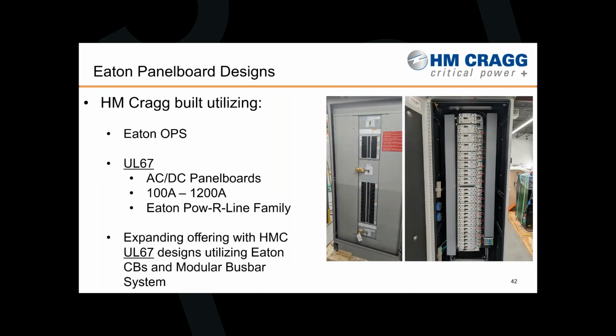When it comes to panel boards, we're utilizing a lot of the Eaton OPS program to develop distribution around them. As mentioned previously, we use panel boards in switchboard designs, which carries another level into PDU or RPP designs. Under UL 67, we can design distribution panel boards for AC or DC applications, ranging between 100 amps and 1200 amps in that standard offering.